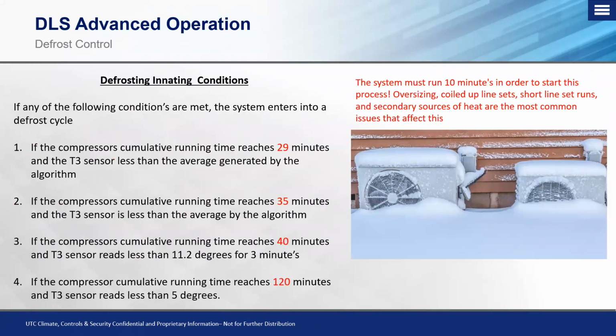So let's talk about the hot topic, especially with this year. Defrosting has certainly been a hot topic in 2021. So this slide is going to be extremely important to make sure that you guys understand how we initiate defrost and also how misapplication, either through oversizing or having additional auxiliary heat sources, can cause defrosting issues. So when we start talking about defrost, before we start looking at certain conditions that need to be met, we need to understand that these systems must run 10 minutes in order to start this process.